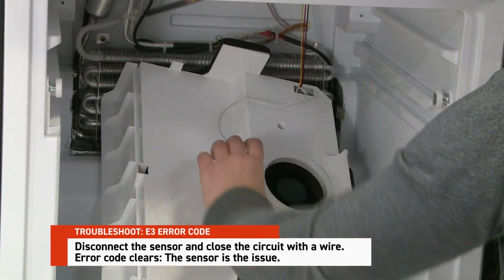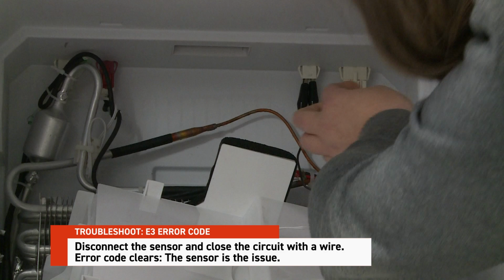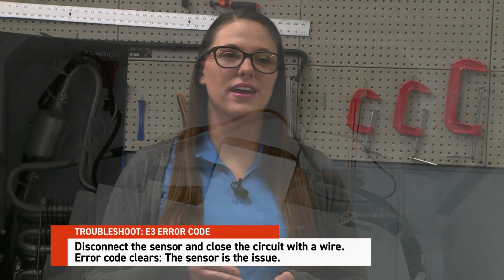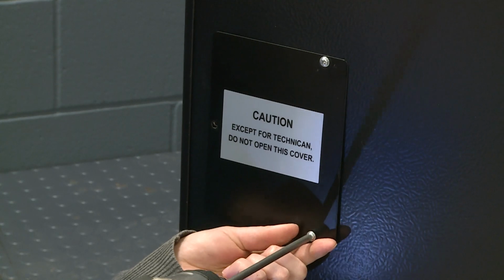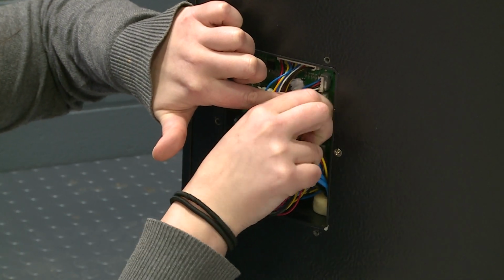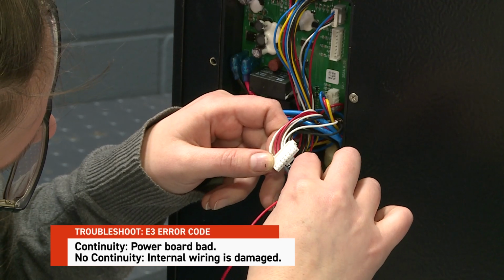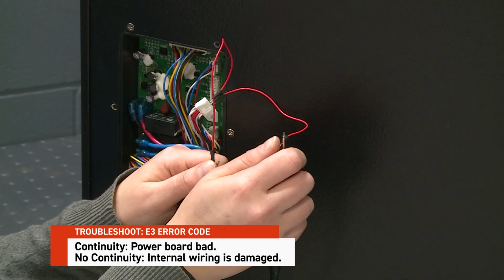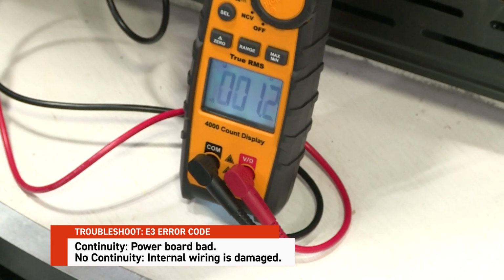Disconnect the sensor and close the circuit with a wire. If the error code clears, the power board and the wiring are fine and the sensor is the issue. This is fixed by replacing the freezer duct assembly that houses the sensor. If the error code persists, move on to the next step, checking continuity. Use a multimeter to test the connection at the power board and verify continuity of the sensor harness. If there's continuity, the power board is the culprit. If there's no continuity, the internal wiring is damaged. By following these steps, you'll be able to pinpoint the cause of the E3 error code and determine the appropriate fix.